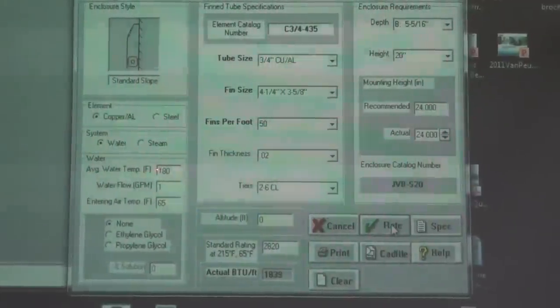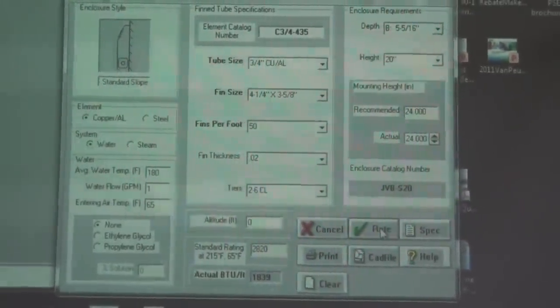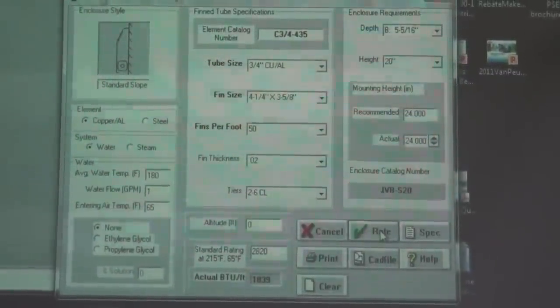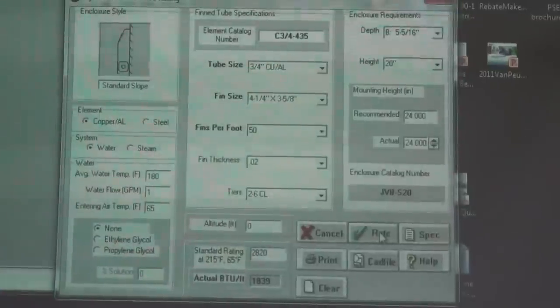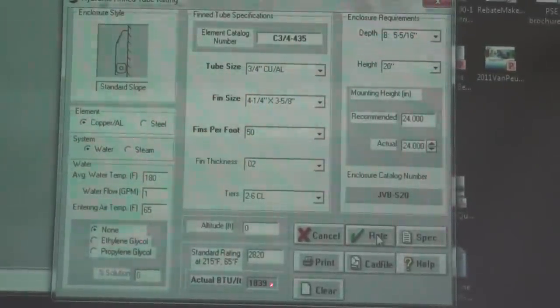And then you have to put it back, then you have to figure out what your new average one is. Because you can't assume, everyone assumes it's 20 degree drop or 30 degree drop, but until you figure it out for each length of run, you won't know what that is. The iteration only takes about two times.